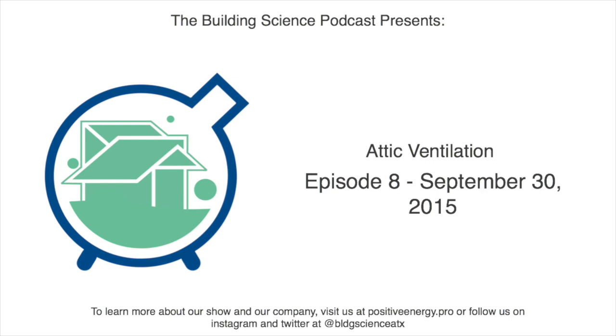So attic ventilation is in the codes, and it also seems to make sense, right? It's hard to get past things that make sense. We can just see the little arrows where the air is going to flow in through the soffits, and then it's going to rise because it's hot, and go up and out through the ridge vents. The problem is, that's not how it works. Those forces are not big enough, neither are the holes. When attic ventilation does work, when air is exchanged through those vents, it's based on pressure differences created by wind. So wind drives attic ventilation, not the stack effect. But as you'll see, I think that's kind of beside the point.